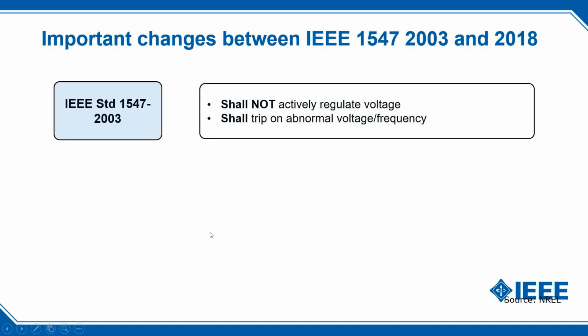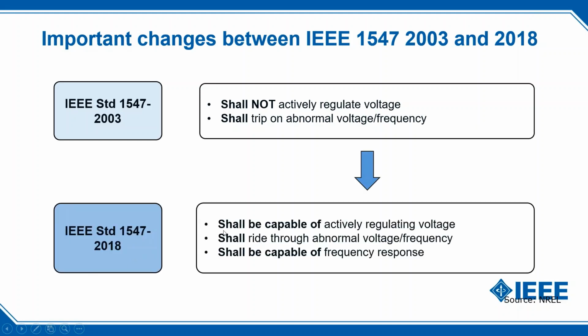Another way to look at the change in that area for performance under normal conditions: if you look at the original standard, many of you are familiar with it, it basically says you shall not actively regulate voltage at the point of connection, and you shall trip on abnormal voltage or frequency and reconnect on your own in 5 minutes. The new standard, or the revision, says all DERs shall be capable of actively regulating voltage. It's a little different from the previous one. You shall ride through abnormal voltage and frequency conditions, and you shall be capable of frequency response if desired by the electric power system operator.